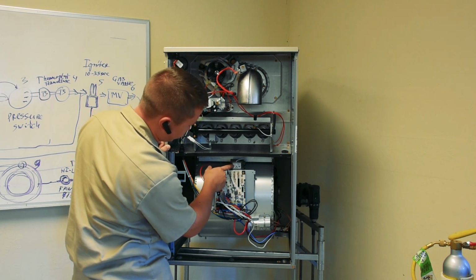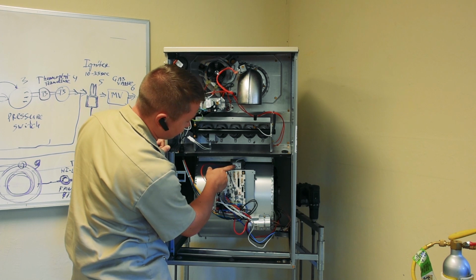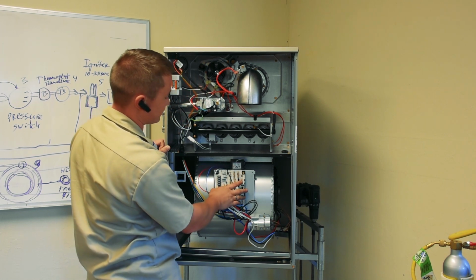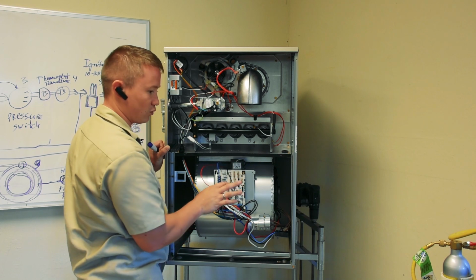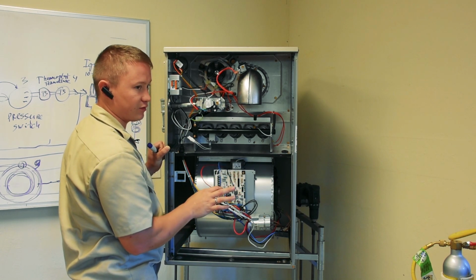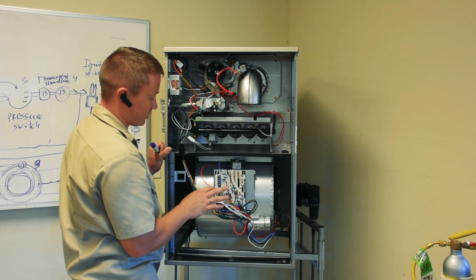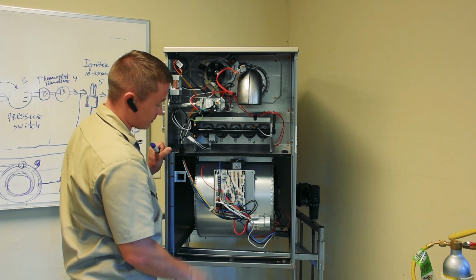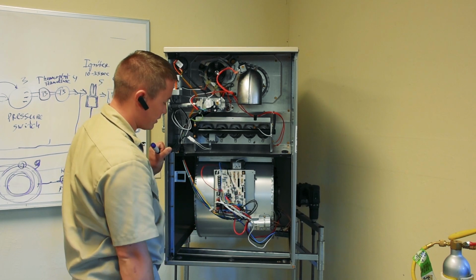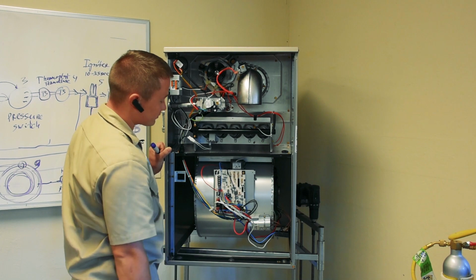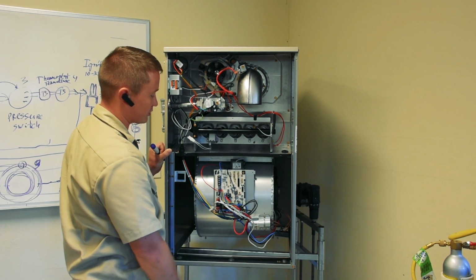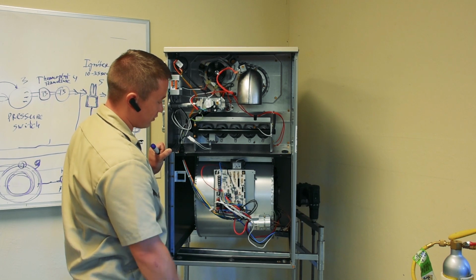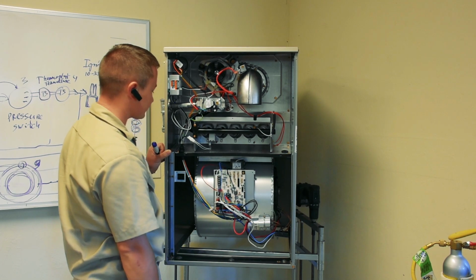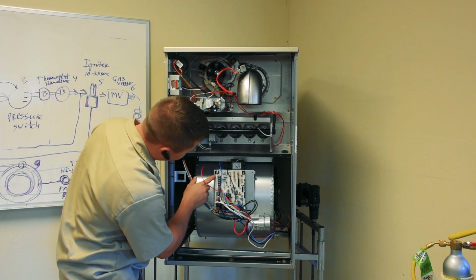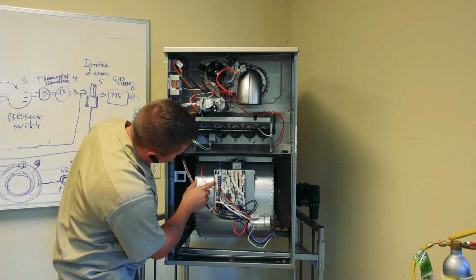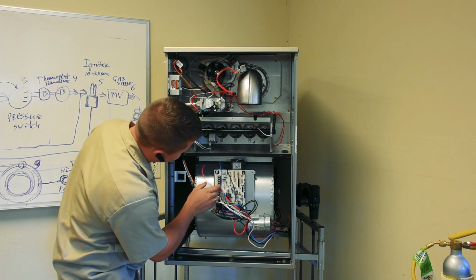This transformer is transforming 120 volts AC to 24 volts AC, and this control board has two circuits. One is a 120 volt circuit and another circuit is a 24 volt AC, alternating current, circuit. Okay, low voltage circuit and high voltage circuit. Some devices on this furnace use 120 volts, some devices use 24 volts, but it doesn't matter. Okay, here's what we have: connectors, like I said, W, common could be not used, doesn't matter.